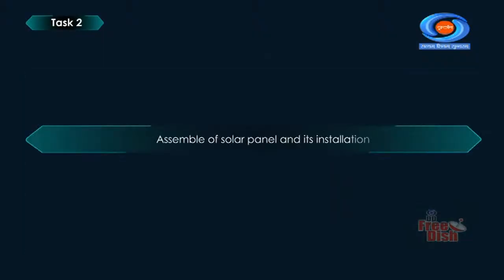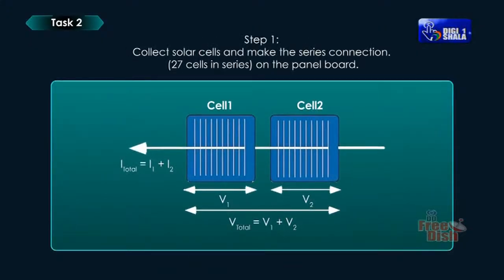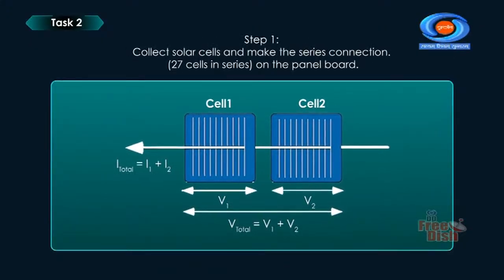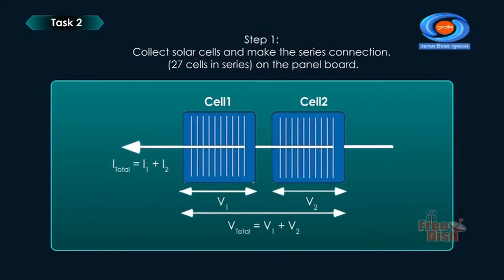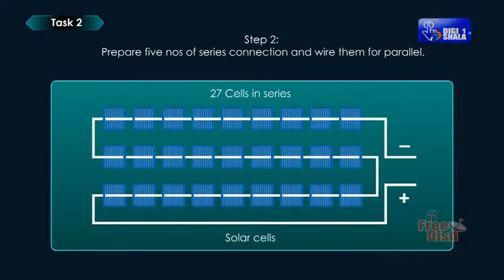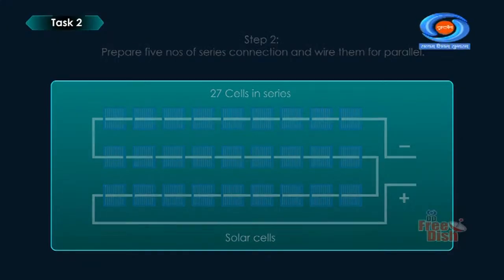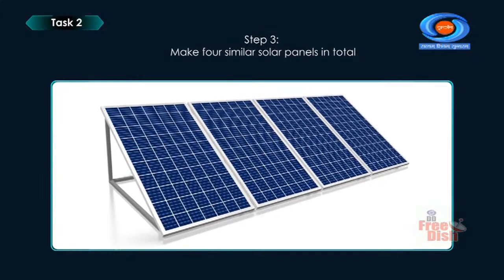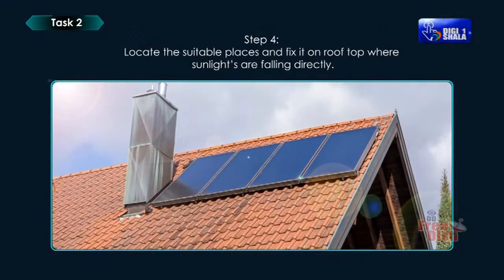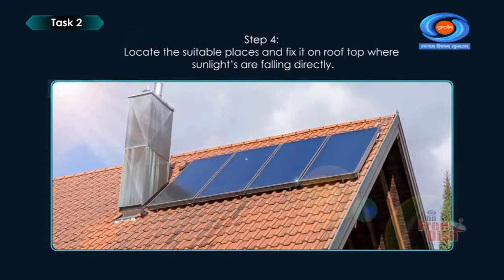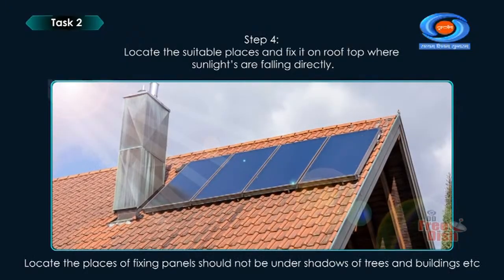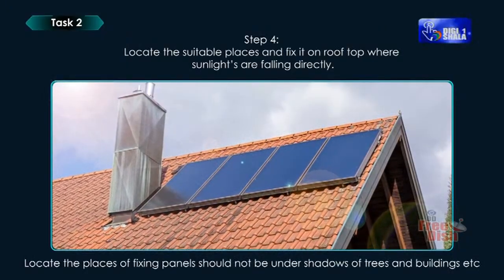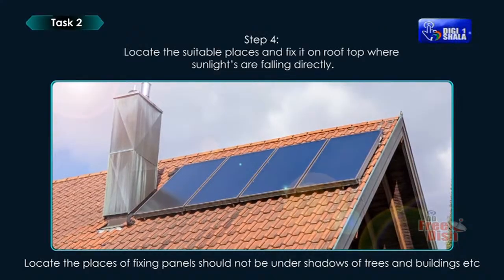Task 2. Assembly of solar panel and its installation. Step 1. Collect solar cells and make the series connection, 27 cells in series on the panel board. Step 2. Prepare 5 series connections and wire them in parallel. Step 3. Make 4 similar solar panels in total. Step 4. Locate suitable places and fix them on the rooftop where sunlight falls directly. The places for fixing the panels should not be under the shadows of trees, buildings, etc.